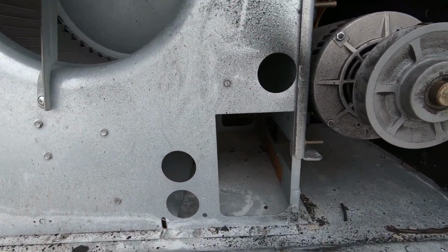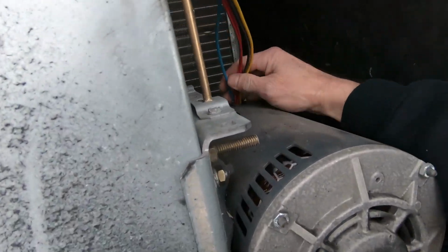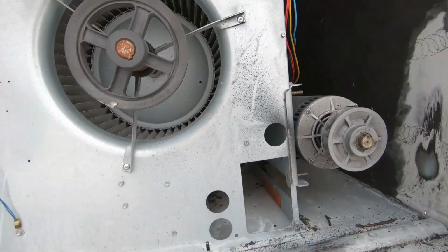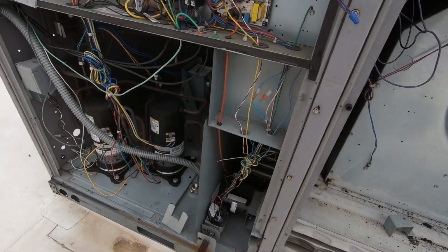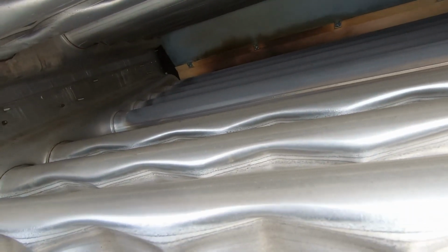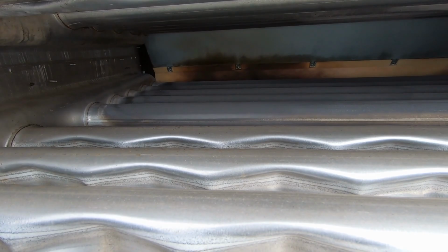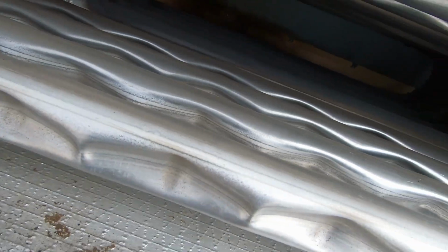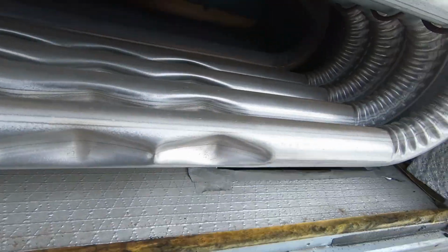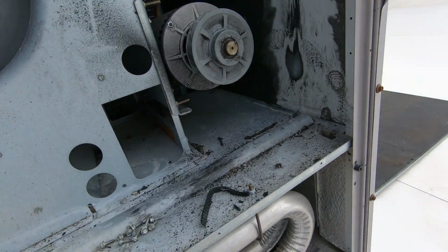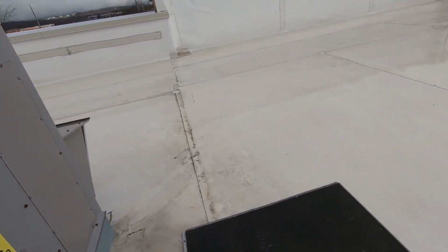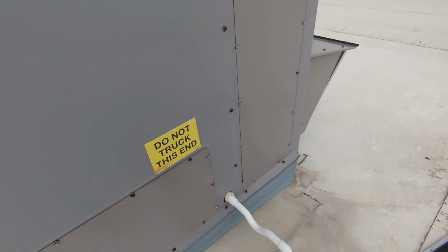Wonder if the motor's cooked. We're gonna check. This could have been bad. This could have been really bad. Ooh, that condensate pan is black. Looks like it got awfully hot. I'm gonna get on the other end of this, and we're gonna check the heat exchanger from this end as well.